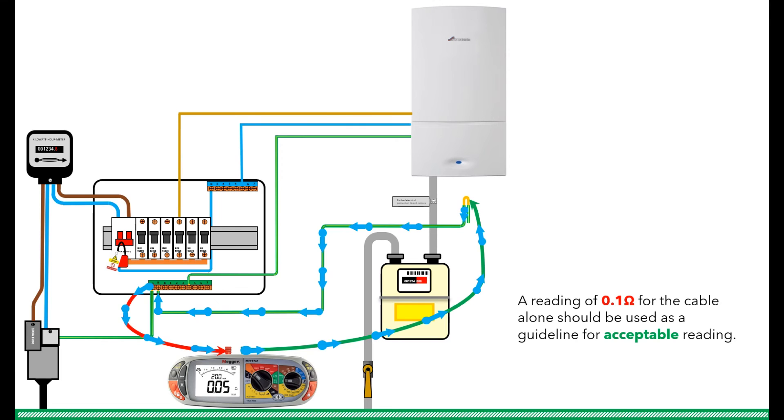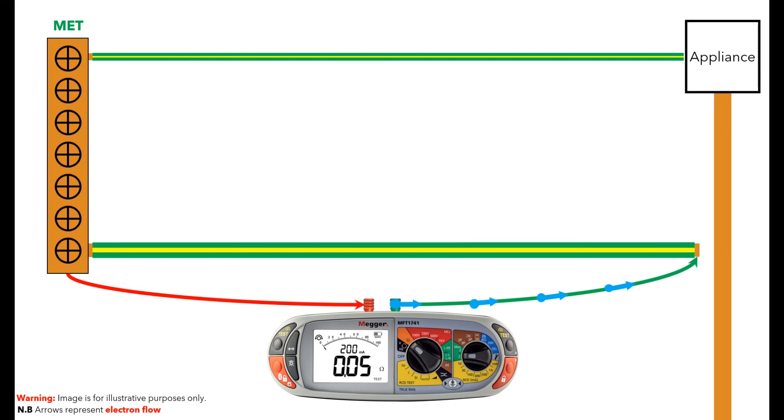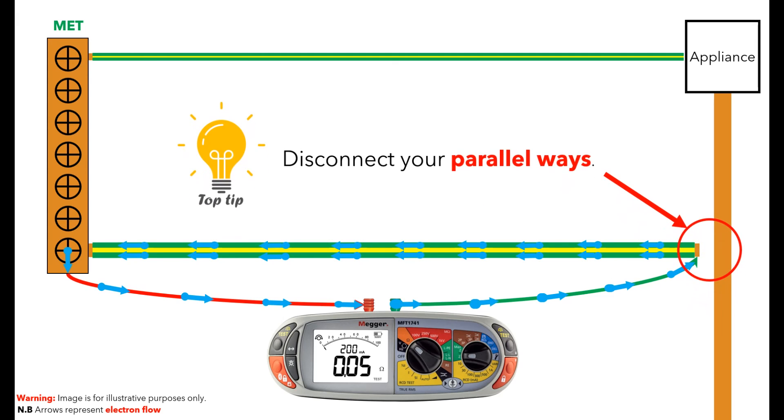Now when you test the conductor, the electrons can only flow in the main bonding conductor and not through any other parallel conductors. If we bring that back to the simplified model, we can now see that because the main bonding conductor is disconnected, the electron flow is only possible through the main bonding conductor as this is the only path back to the batteries in the MFT.